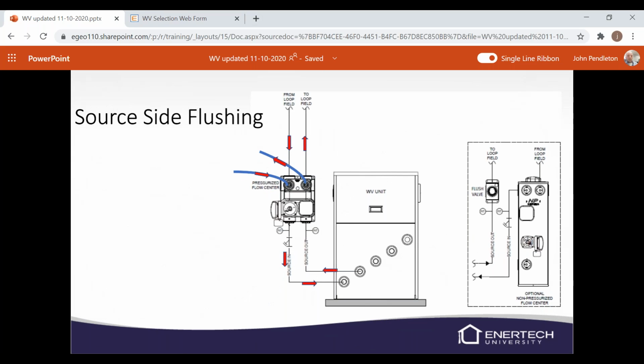Source side flushing: make sure that when you're flushing, those 2 little blue lines indicate the hoses coming in from the flush cart. Make sure that you flush in the normal direction of flow. We've got that strainer in there, and we want that strainer to help catch stuff as we're flushing. So make sure that we're always flushing in the direction of flow through the unit on the source and the load, because we have a strainer on the load side as well. So we're going to have to flush in the direction of flow on both the source and the load.